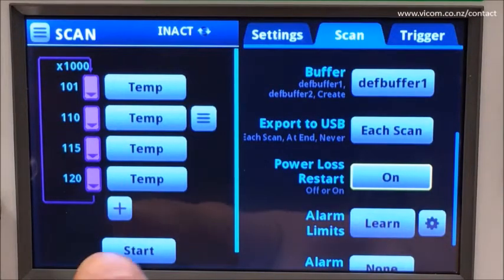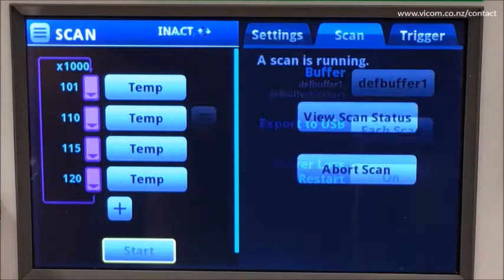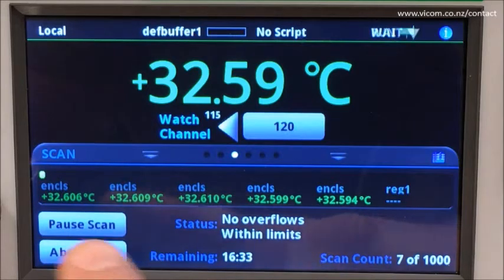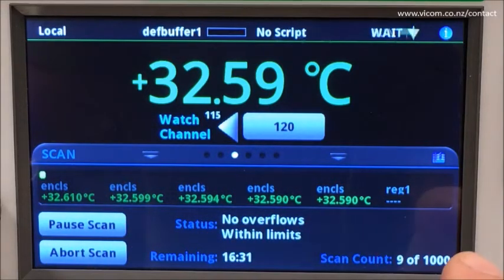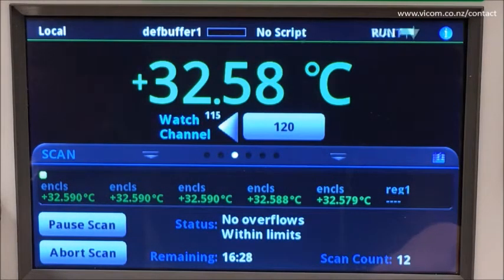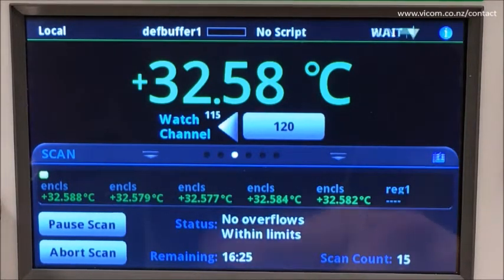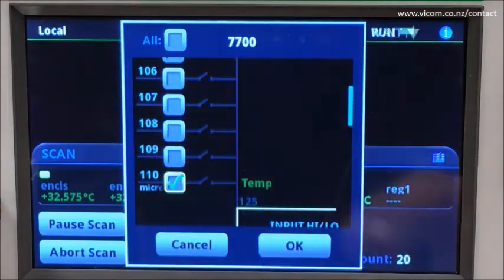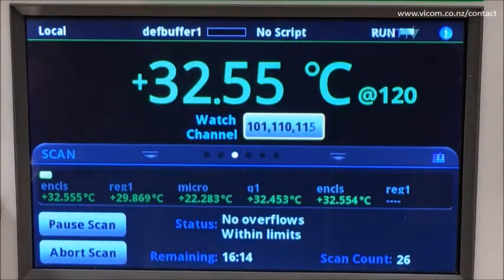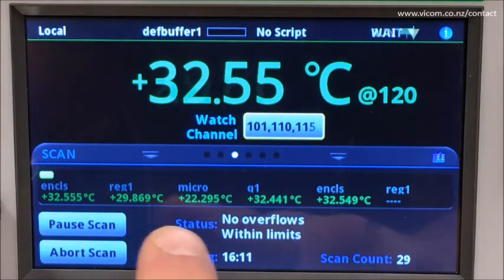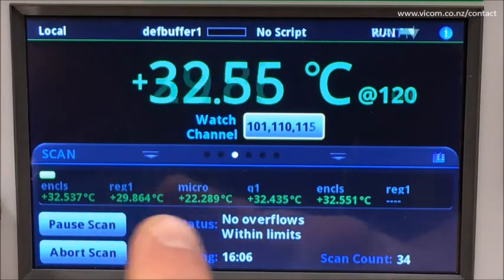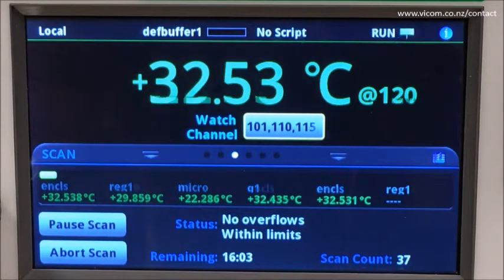Let's go ahead and start this scan and view the scan status. You can see on the carousel we're monitoring the last channel that was configured in our scan channel setup. Let's look at each individual channel. Now you can see that the carousel is monitoring each of the four channels, letting us know by the label we applied what measurement goes with what channel.